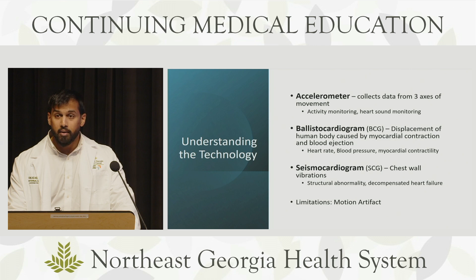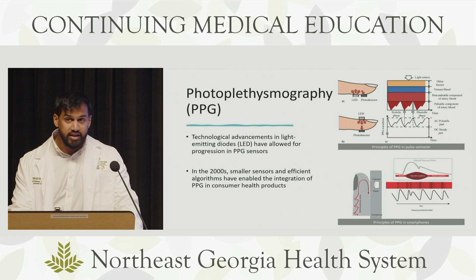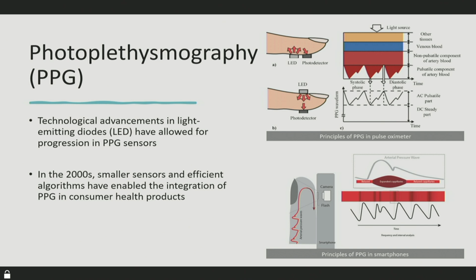Photoplethysmography, probably my last time saying that during this presentation, or PPG, is a technology that has really benefited from advancements in LED and has allowed for progression in PPG sensors. In the 2000s, smaller sensors and more efficient algorithms enabled the integration of these devices into consumer health products. These work by using an LED that shines light, usually in a green or infrared spectrum, onto the skin. Blood vessels in the skin absorb that light, and the amount absorbed fluctuates with the pulsatile flow of blood. A photodetector in the device then measures the amount of light reflected back, which creates a waveform that corresponds to the blood volume, which changes with each heartbeat.